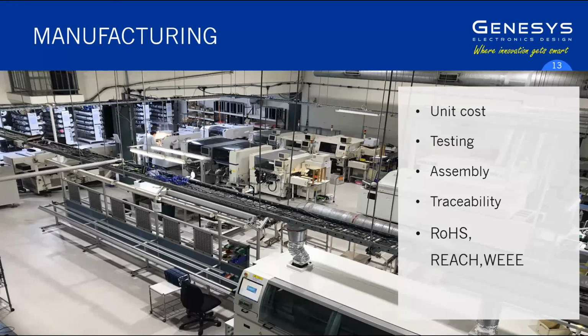A key aspect of any medical device is traceability, and that's knowing exactly where each component came from and where it's gone. And the same also applies from the point of view of design traceability. Did you want to just briefly comment on design traceability, Jeff? Yeah, effectively, the medical regulatory standard requires the developer to trace from user needs, which is the fundamental statement of what the user wants the product to do, through all the technical design documentation and right through to verification and validation testing, and ultimately to product testing and manufacture.